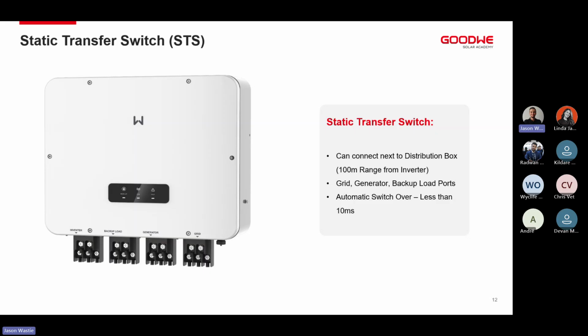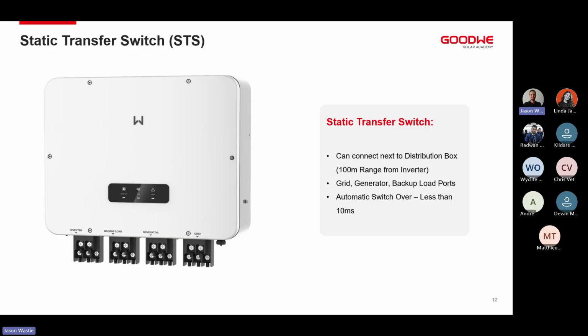Obviously, when switching occurs, we're using it through a contactor or a relay, and contactors and relays have a certain amount of lifespan. Meaning that if we're looking at the STS now, we're going to continuously be swapping power around between grid port, generator port, and inverter port going into the backup load. Again, the inverter is meant to withstand this. The inverter is manufactured to withstand this. However, a contactor and a relay can fail over time.